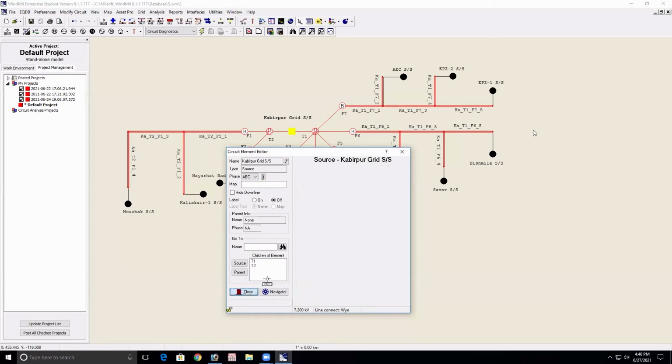All the wrong data inside your source, all the wrong data, you need to correct it. Now it is clear. So next, your bus voltage is 100. You will put your bus voltage 100. Look, first select these things: line to line voltage 1,32,000 and bus voltage 100. Because I want the voltage same as it is, 1,32,000. Then your next task is just to close it. So two things you need to correct: the 1,32,000 and bus voltage 100. Then close it. So the first thing is gone.